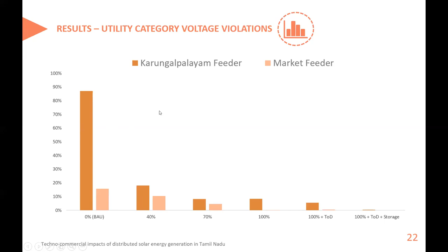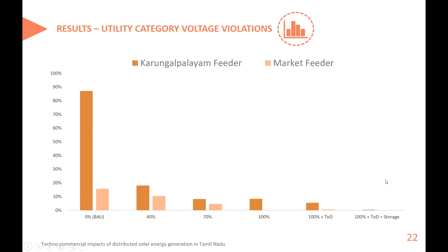As you can see, for Karungalpalayam feeder, we observed that around 87% of the time the voltage is violating. With the introduction of solar and different strategies, that is TOD and storage, we could drastically reduce the voltage violation for the whole year. The same is the case with market feeder, as you can see here. With storage, we could bring most of the voltage, including tail end voltage, within the acceptable limit.